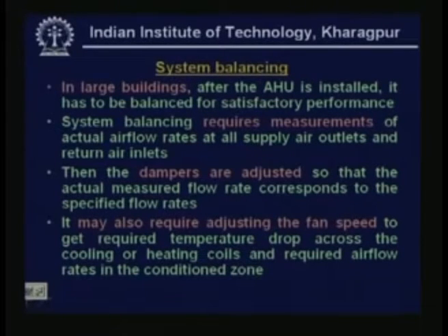Ultimately, why do we do system balancing? Let us say that you have carried out the cooling load calculation, then you have designed the ducts, you have selected the fan, you have installed everything. So, finally, you have to get the required performance, that means you have to get the required temperatures in the conditioned space. This depends upon the temperature of the supply air and also upon the supply air flow rate. So, you have to make sure after you install everything that you are getting the right amount of air at the right temperature.